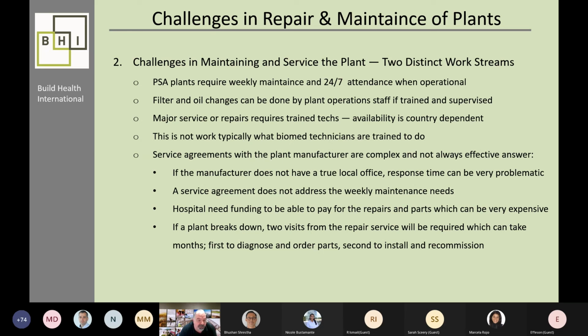Service agreements with plant manufacturers are complex and not always an effective answer. If the manufacturer doesn't have a true local office, response time can be very problematic. We see that when plants break down, they often stay broken down for months, because it typically requires a minimum of 2 visits to repair the plant: first, the service company has to diagnose the problem and order parts, which can take a long time especially clearing customs, and then they have to go back to install and recommission them.